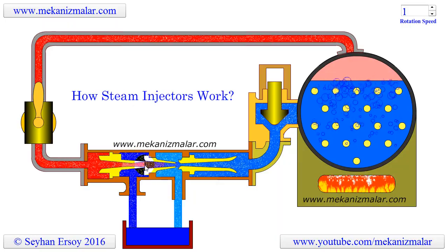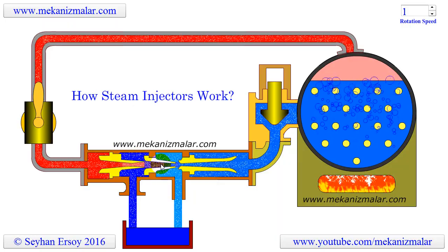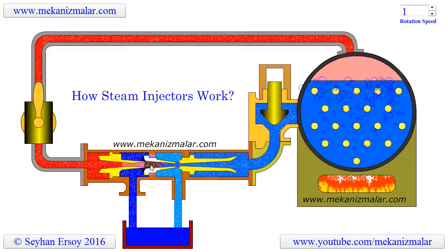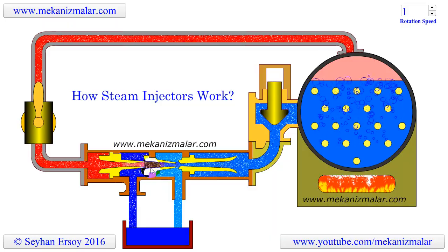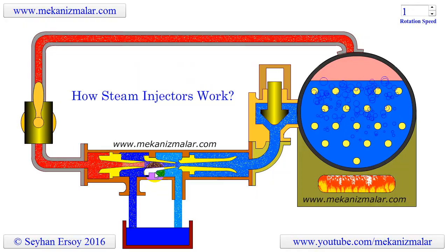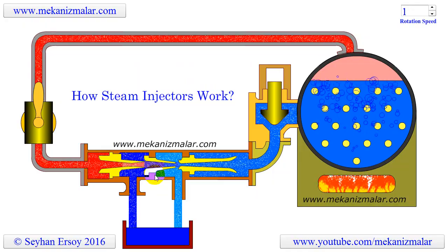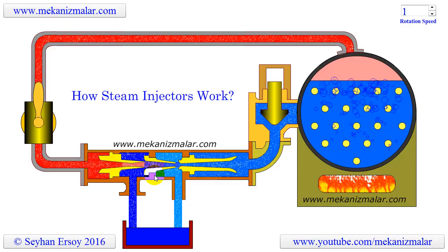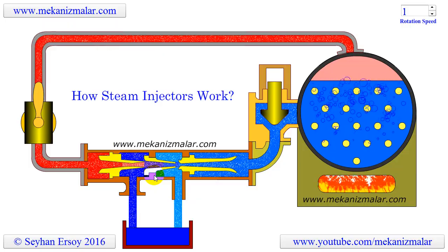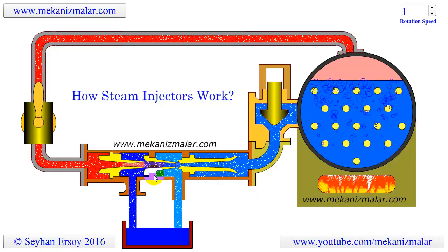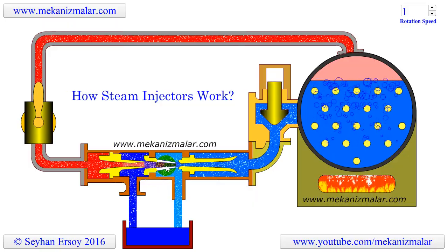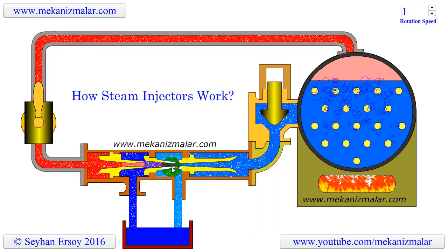During the combining process, the steam begins to condense and the water begins to get warmer. The speed of the water is increasing due to the hammer effect of the steam jet, while steam disappears from the flow by condensing as water. Further narrowing of the combining cone increases the speed of this water.